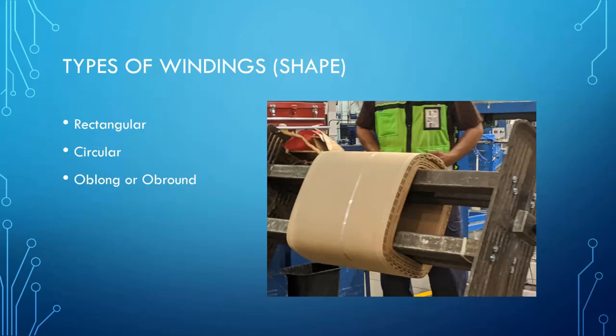So there are a few different types of windings, and by windings, I mean the shape of the windings. There are, of course, rectangular windings that can be built with either a wound or a stacked core. There are circular windings that are very strong during a short circuit. And then there's the oblong or ob-round windings, which have characteristics of both. The ob-round winding is mostly rectangular with the corners sort of cut off, if you will, and I'll show some pictures of that. But here to the right, you'll see a photo of a gentleman at a transformer manufacturer who is winding a rectangular coil. And you can tell by the rectangular mandrel that that transformer is obviously going to go onto a rectangular core.